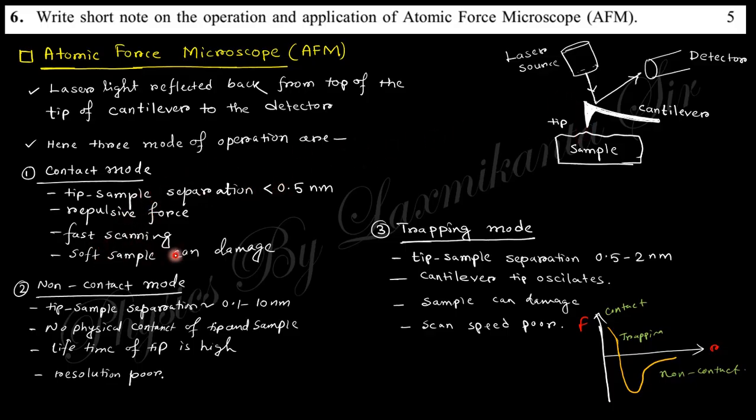Contact mode means tip and sample are in contact with repulsive forces and fast scanning, but soft samples can be damaged. Non-contact mode keeps them separated so the tip has high lifetime. Tapping mode operates in between.